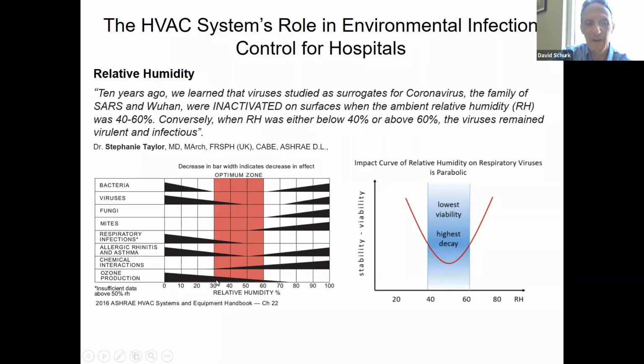So we can see that the optimum range is considered to be somewhere between 30 and 60% relative humidity. If we vary out of that range, either drier or wetter, the possibility of those issues increases, particularly with regards to low relative humidities. There are certain concerns I'll go into detail on in a slide or two, but more current research specific to respiratory viruses has tightened that range to a window of 40 to 60%. It tells us that if we vary outside this range, either higher or lower, it has a profound impact on that respiratory virus's viability or effectiveness, and also its decay rate, or length of life.